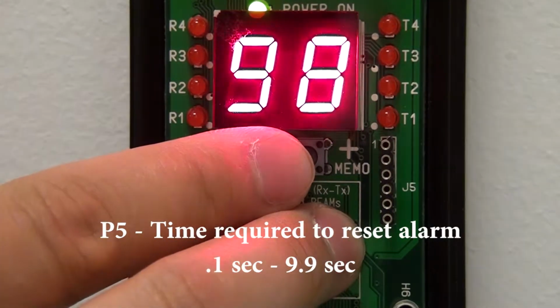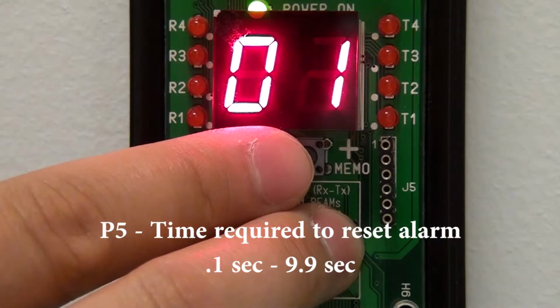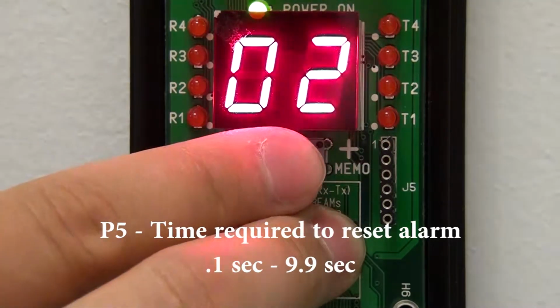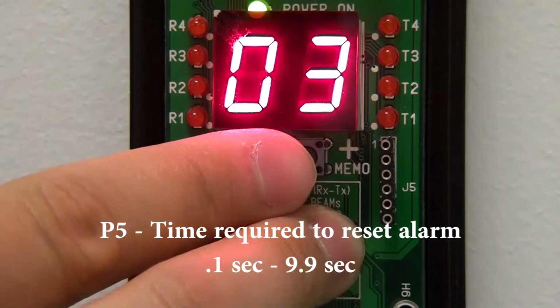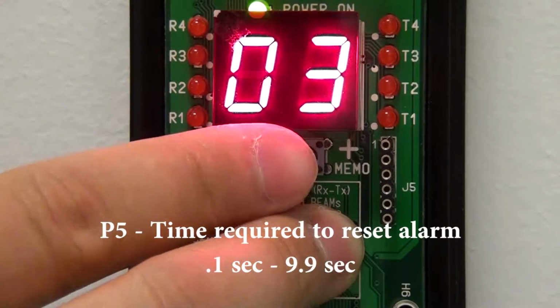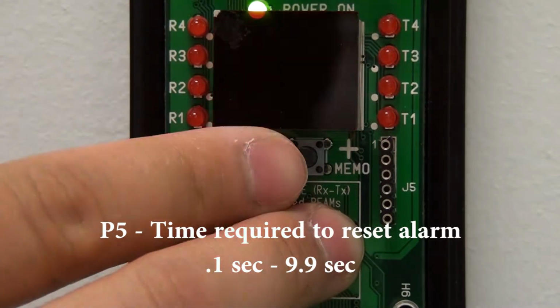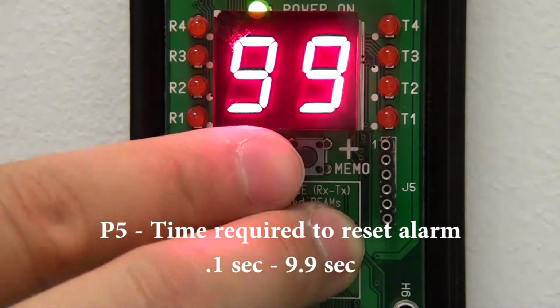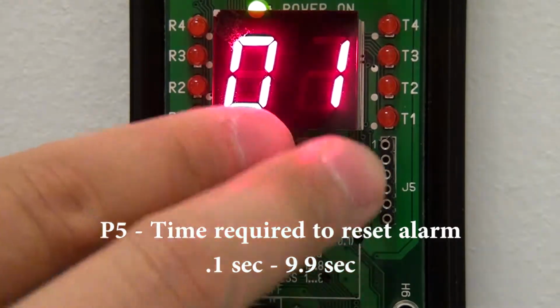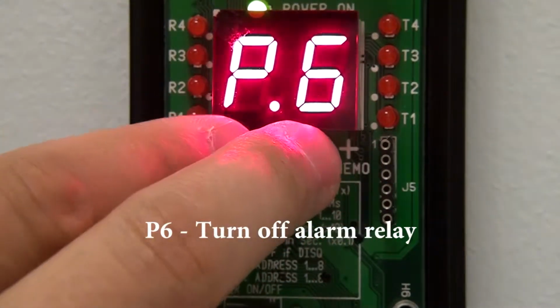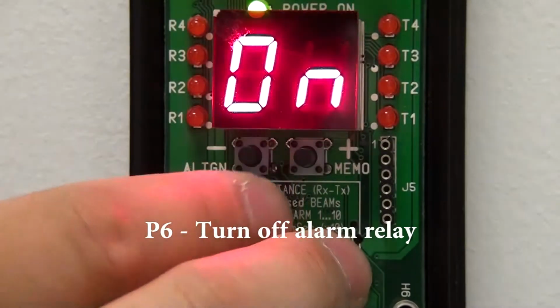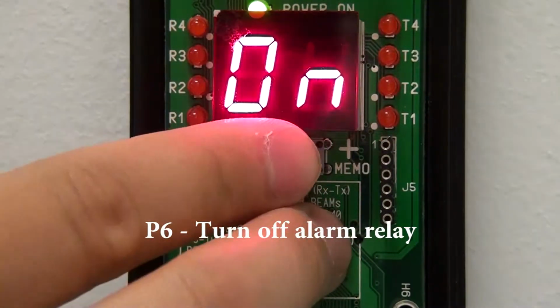And this is the amount of time between alarm tripping and resetting. So then if someone triggers the alarm again, it'll send another signal, or if you wait, for example, 10 seconds, you have that window before the alarm resets. And P6 is to turn off the alarm relay, so we can turn it off or on.